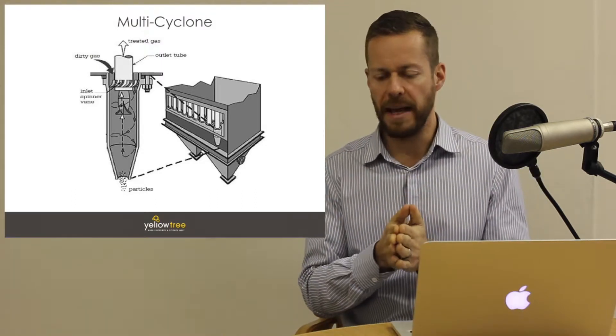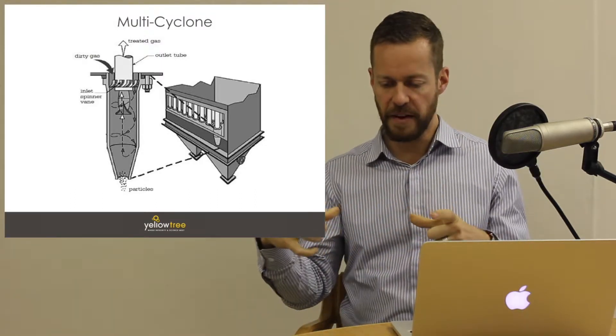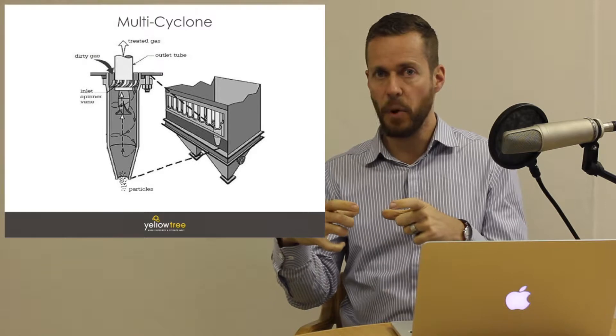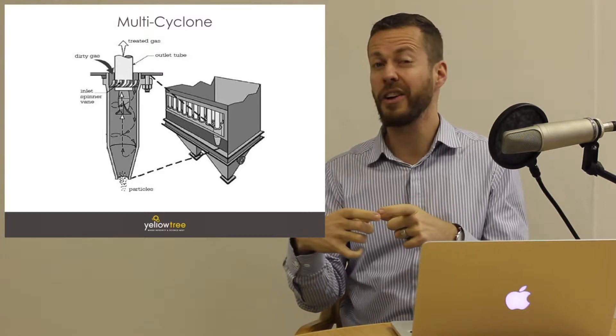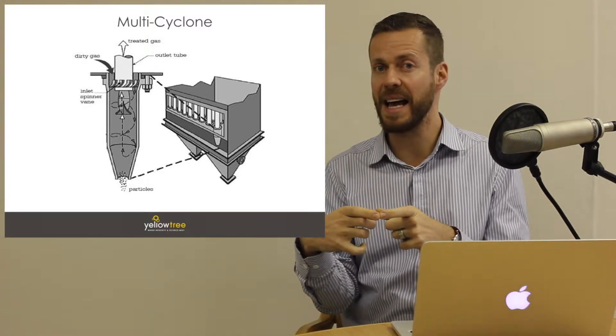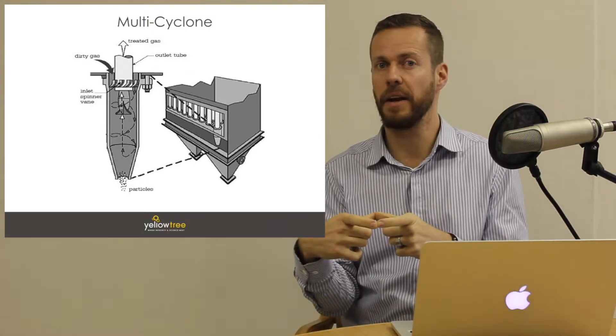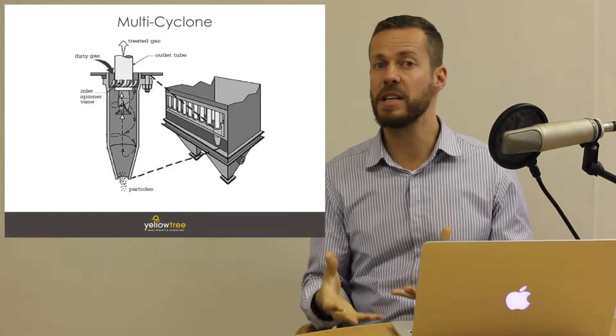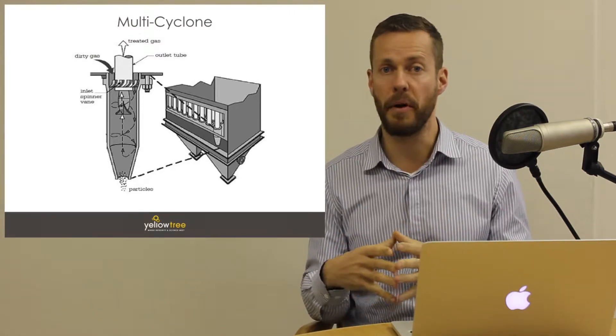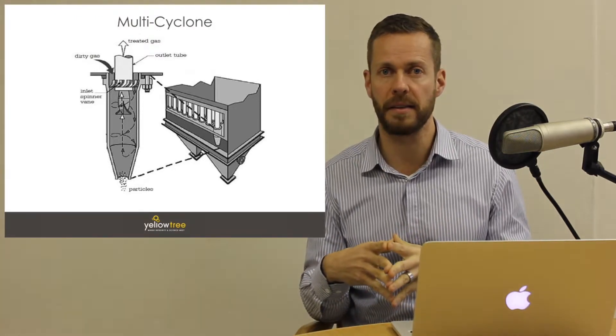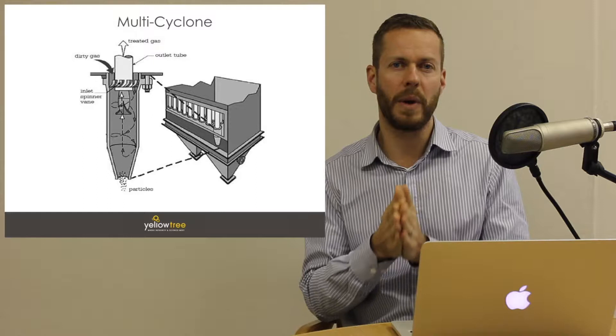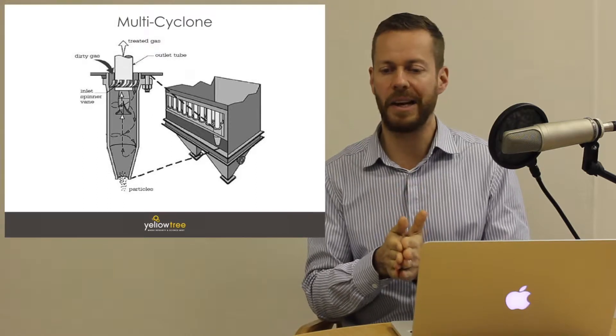So what we learn from that is that if a cyclone can be made smaller, we can increase the centrifugal forces inside it. More centrifugal force means better separation of the particles. And for that reason, we have multicyclones.